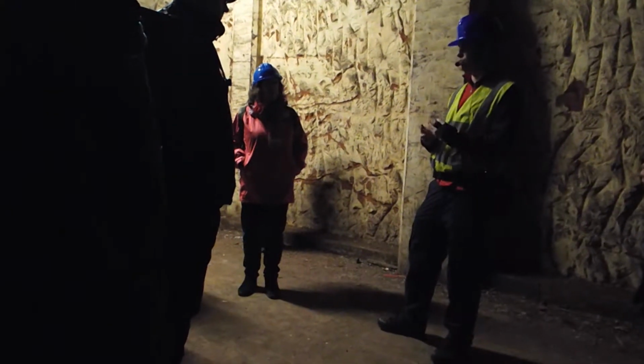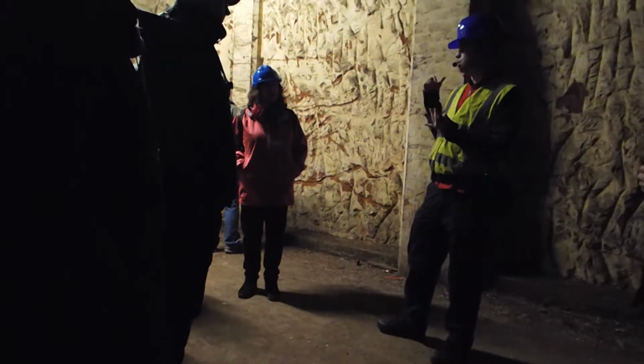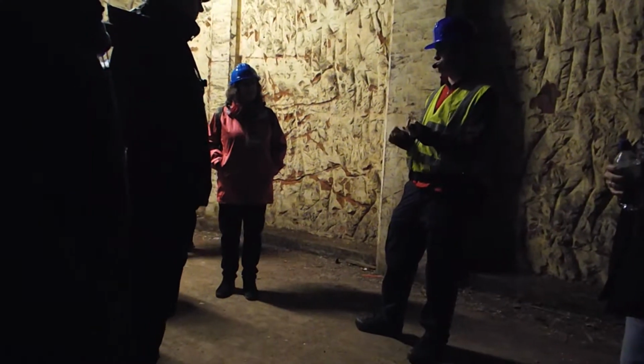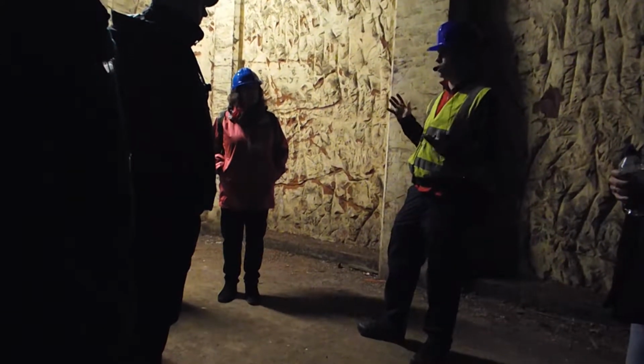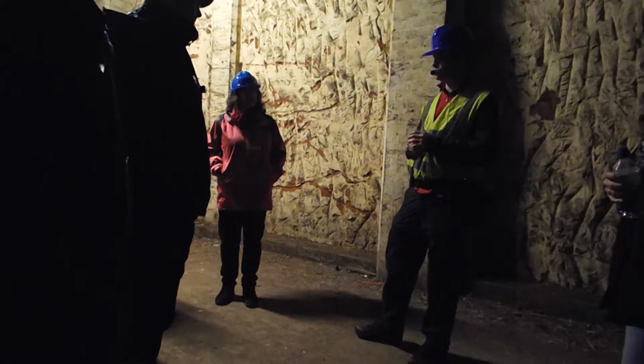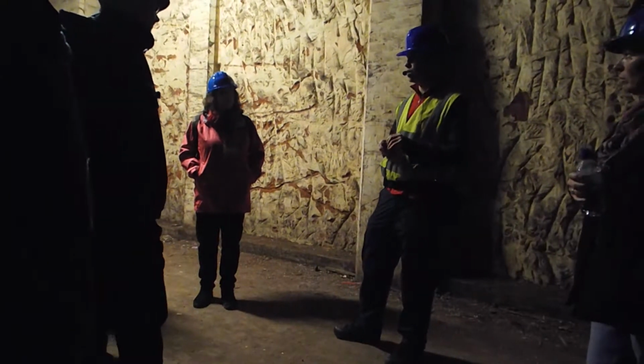So now we've put an alarm system on the second generator, so if any of the levels drop, we know. There's an audible alarm, which you can hear throughout the regional government headquarters, so you can leg it over and switch systems off. And there is a visual alarm as well. We've also put a massive tree trunk outside the door of the radiator room outside, so people can't get into that.